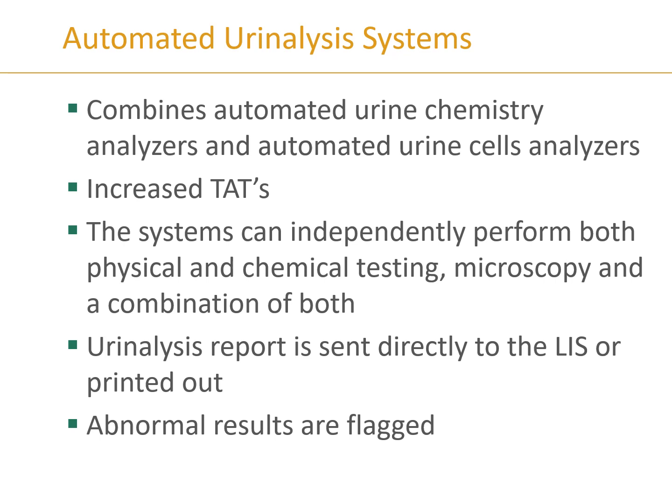Automated chemistry analyzers combine the automation of urine chemistry analyzers with the automation of urine cell analyzers into one system. This increases turnaround time because you are not dipping, spinning, and looking at samples separately — it runs everything at once, performing physical examination, chemical examination, and microscopy together. Reports can be printed or transmitted via LIS, and anything abnormal is flagged.